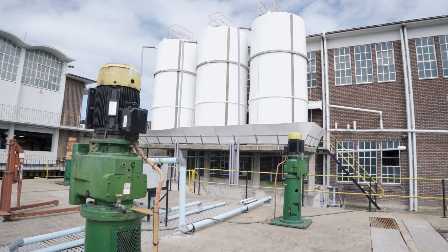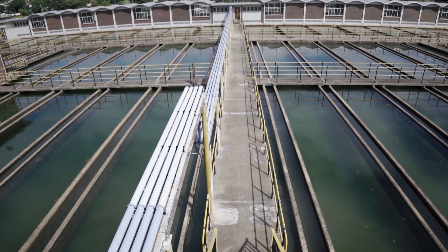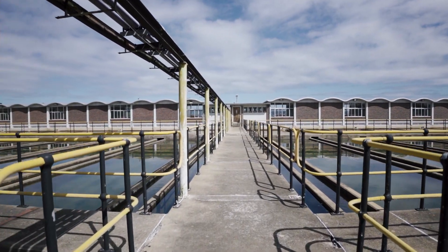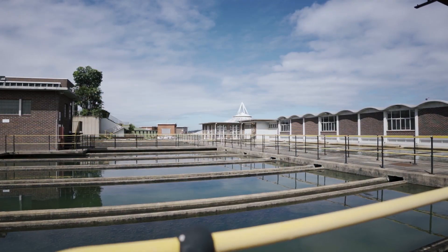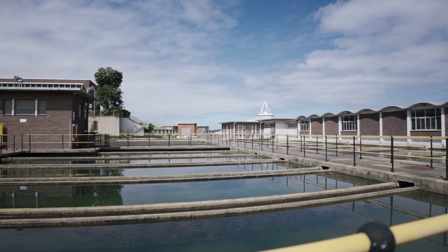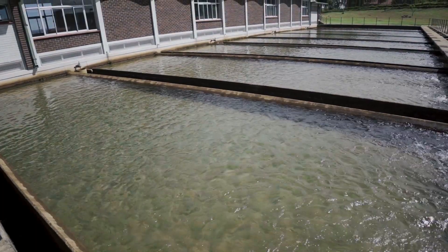The water then flows into large settling tanks. Here, the coagulant helps to bring the small dirt particles in the water together. It works like a magnet to form lumps known as floc. Floc sinks to the bottom of the tanks to form a sludge blanket. As the flocs settle, the cleaner water on the surface flows to the sand filters.